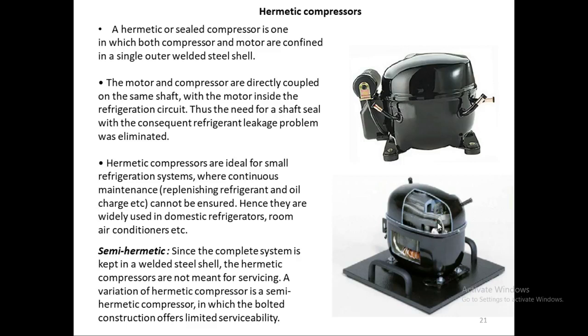Once your compressor is gone bad or your motor is gone bad, you have to throw away your entire compressor and put a new one in there. But to avoid that, we have the semi-hermetic one where this upper portion is bolted down with the bottom portion, so that it can be repaired. Some repair work can be done on it. So this is the top part and this is the bottom part.